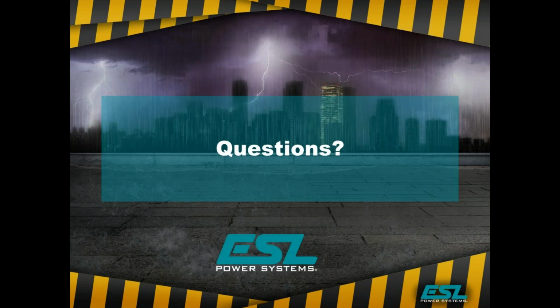Well, hopefully this helps to allow you to make some very cost-effective, very efficient designs. We're seeing a lot more instances where emergency power is now being required on various types of facilities, and people are going back and reevaluating their backup to their permanent generators and whether or not they should be load banking them. I think if you talk to your generator providers, they will tell you that the newer, higher tier, more efficient generators are more susceptible to wet stacking, and therefore really having load bank capabilities is becoming more and more important as you design these systems in, and these higher efficiency generators are needed.